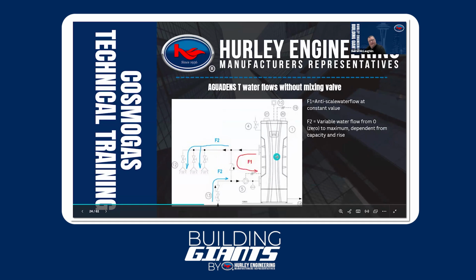You can see they've got 2 distinct flow circuits that they're concerned about. So the first flow circuit is going to be F1, and this is the critical one. This pump down here has got to maintain the flow that we want, to be able not only to put out the hot water we need, but to prevent the scaling and limescale buildup on the heat exchanger. The flow circuit 2 is just going to be the load of your circuit itself and what the hot water demand is in that building, right? So keep in mind, again, this is just for industrial applications.